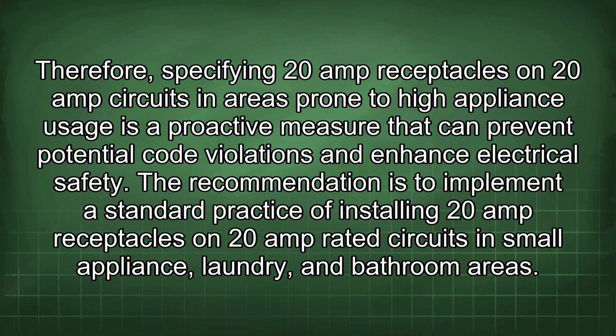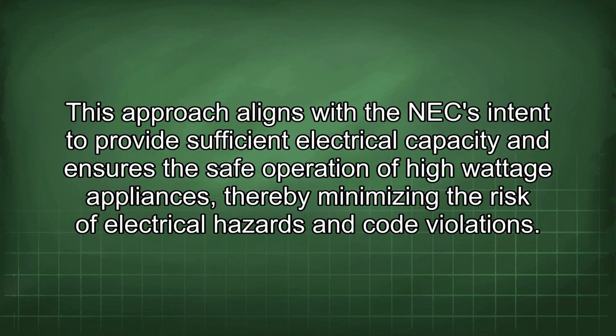The recommendation is to implement a standard practice of installing 20-amp receptacles on 20-amp rated circuits in small appliance, laundry, and bathroom areas. This approach aligns with the NEC intent to provide sufficient electrical capacity and ensures the safe operation of high-wattage appliances, thereby minimizing the risk of electrical hazards and code violations.